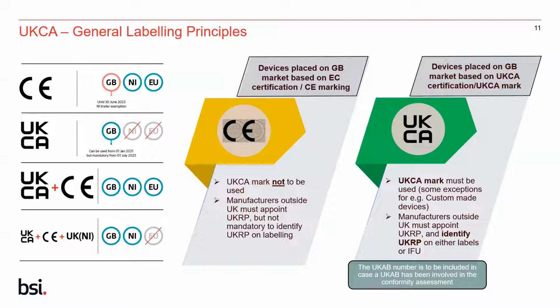Thinking about the two options that allow you to place a device onto the GB market until the end of June 2023, there are two different sets of labeling requirements that do apply. If you are going to place a device onto the GB market based on the CE marking, then of course you shall not affix the UKCA mark because you did not follow the UK legislation. Moreover, in case of manufacturers based outside the UK, a UK responsible person shall be appointed, but it's not mandatory to identify the UKRP details on the labeling.